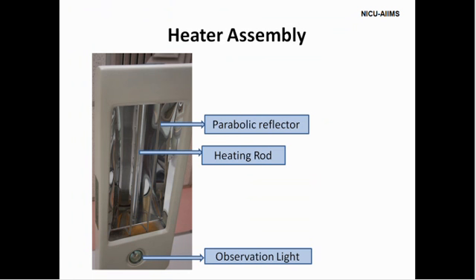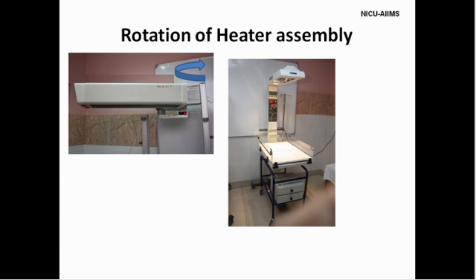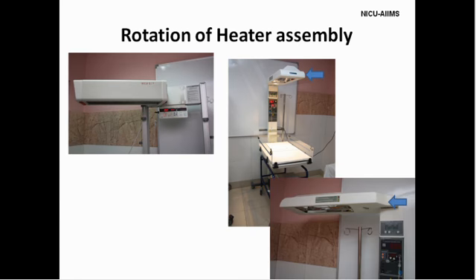Coming to the heater assembly. The heater assembly consists of a radiant heater, which is made up of a ceramic or a cal rod and a parabolic reflector. In addition, most warmers contain an observation light which focuses on the baby bed. While the cal rod or the ceramic is a source of heat production, the parabolic reflector reflects the produced heat onto the baby's bed. In some radiant warmers, the entire heater assembly can be rotated to 90 degrees or at times even 180 degrees to the side for taking an X-ray picture.